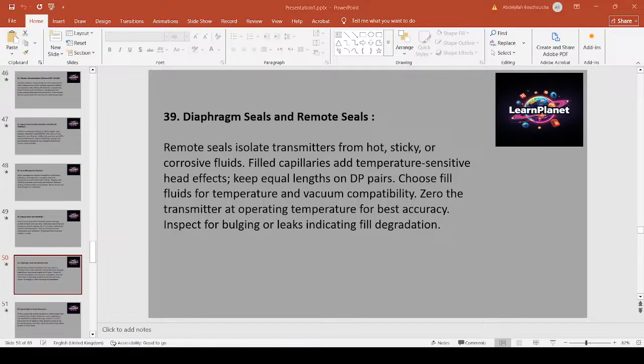Remote seals protect transmitters from viscous, corrosive, or higher temperature fluids by isolating process media with thin diaphragms connected via fill capillary to the transmitter. Capillary lengths and fill fluid introduce head and thermal effects. For a DP pair, keep capillaries matched to avoid differential thermal errors. Choose fill fluids with compatible vapor pressure and temperature range to avoid cavitation or vapor formation. Inspect seals periodically for bulging, which indicates internal degradation or loss of fill. Example, in a hot crude application, use high temp silicone fill and match capillary length to both legs of a DP level pair.